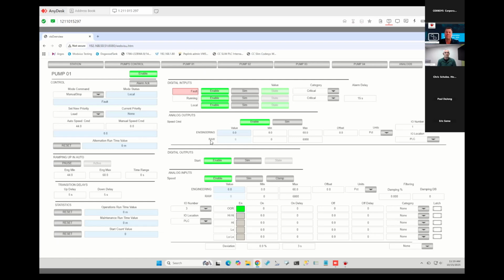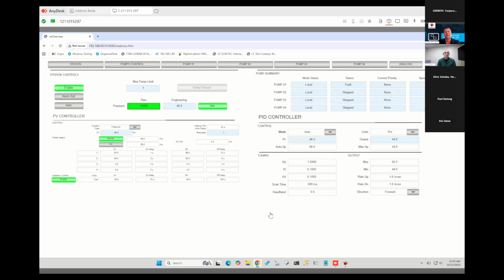So with the Modbus, you have these signals automatically. Your run, your fault, HOA, hand-off-auto, and then any of your outputs and your scaling. So like for this one scaled 0 to 6,000, which would mean 0 to 60 hertz. But you can scale that any way you want because it allows the operator complete control of how the system's working. Under our station screen, this is where the actual fun happens.